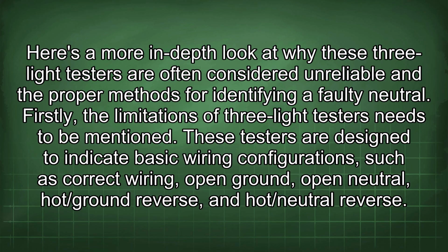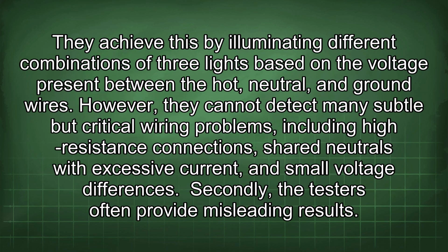Here's a more in-depth look at why these 3 light testers are often considered unreliable and the proper methods for identifying a faulty neutral. Firstly, the limitations of 3 light testers need to be mentioned. These testers are designed to indicate basic wiring configurations such as correct wiring, open ground, open neutral, hot/ground reverse, and hot/neutral reverse. They achieve this by illuminating different combinations of 3 lights based on the voltage present between the hot, neutral, and ground wires. However, they cannot detect many subtle but critical wiring problems, including high resistance connections, shared neutrals with excessive current, and small voltage differences.